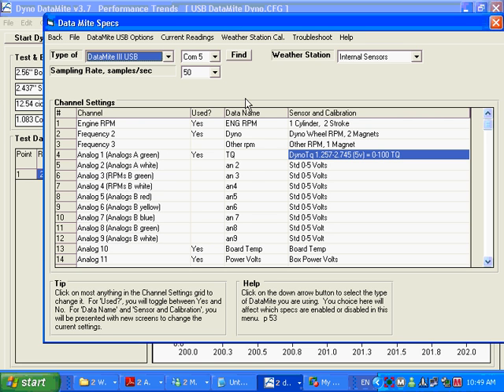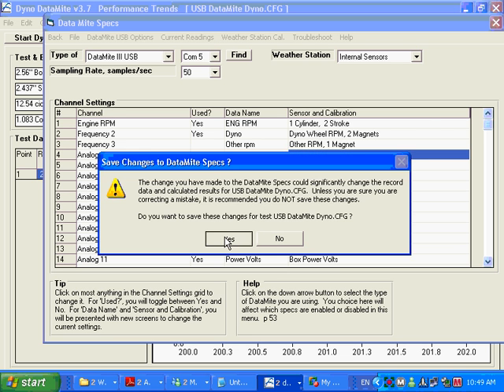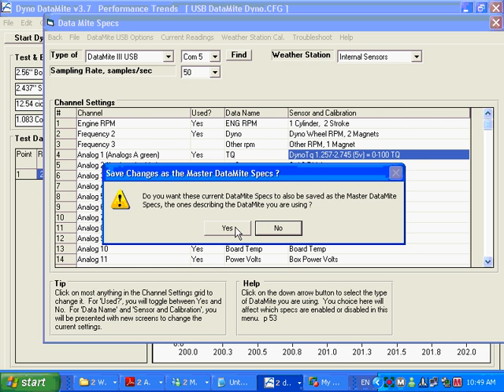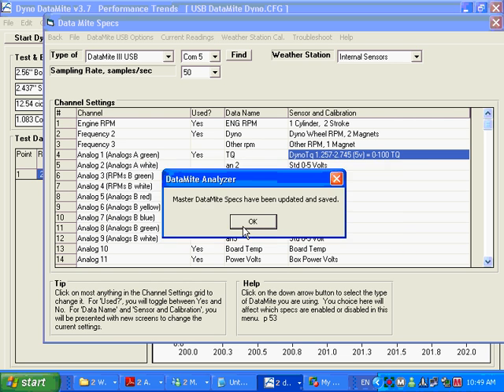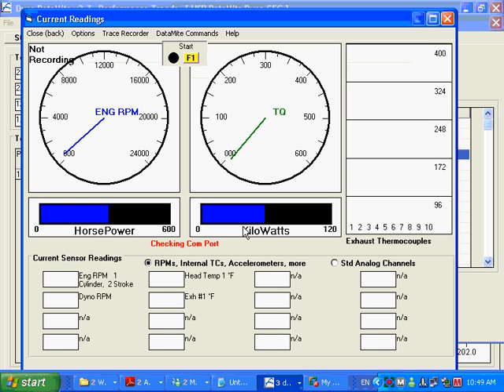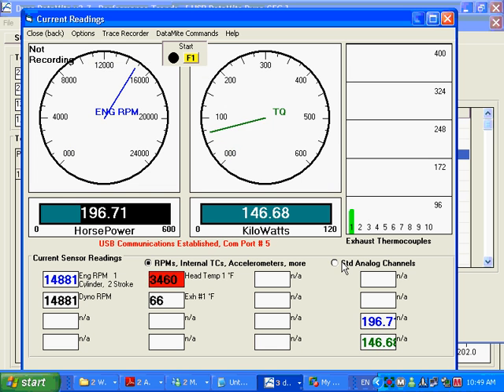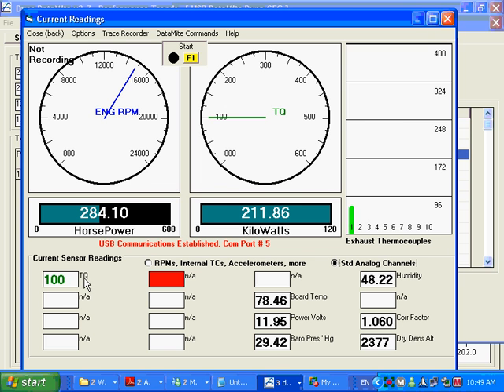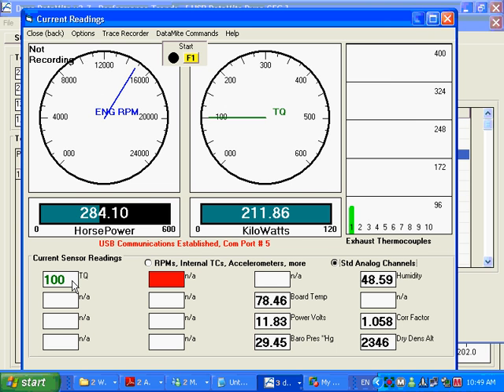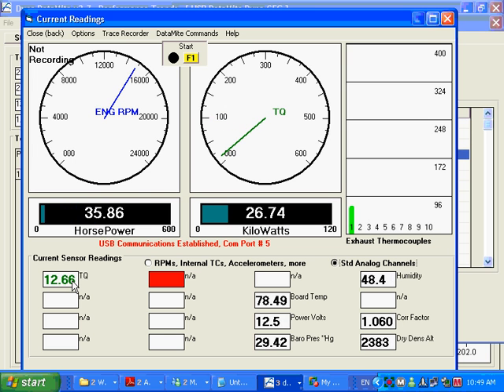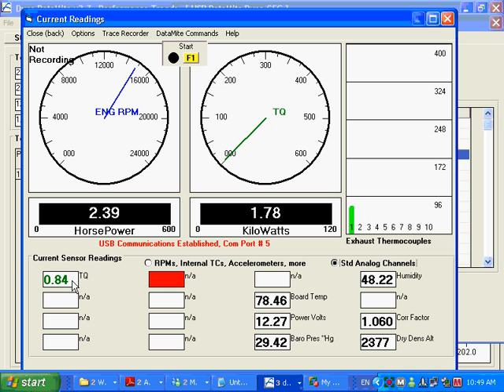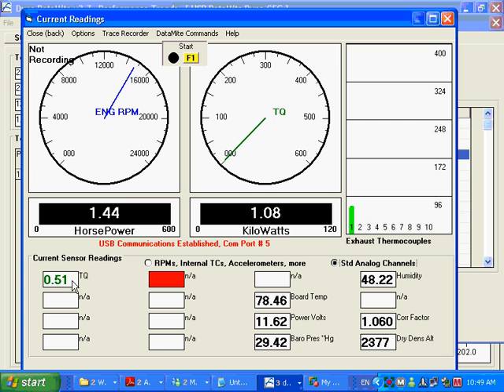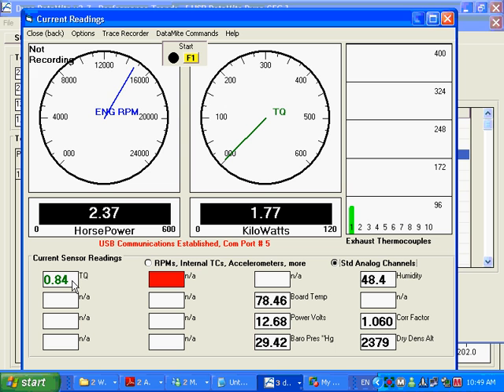Once you do your torque calibration, asking do you want to save things as the master, I said yes. You should be able to go into your analog channels. Here's torque that we put in, and you can see we're still hanging our 100 pounds, our 50 pounds at two feet, and we're getting 100 foot-pounds of torque. Now you should be able to see if you go down to zero, we should be able to get, as you can see, we're very close to zero. So our calibration is working, and you should be able to hang anything on there you want and you should be able to get the correct reading here for torque.